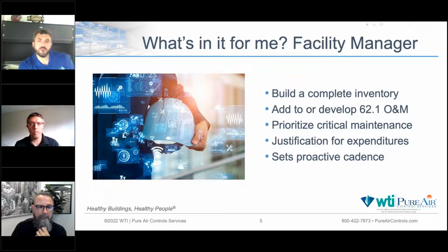I'll never forget one where, high-rise building, a lot of air handlers, a lot of floors, and one of the floors has discharge out of the supply duct. Pieces of material fall down on our desks. What's the knee-jerk reaction? Okay, get in there and clean the ductwork. And months later, that discharge happens again.